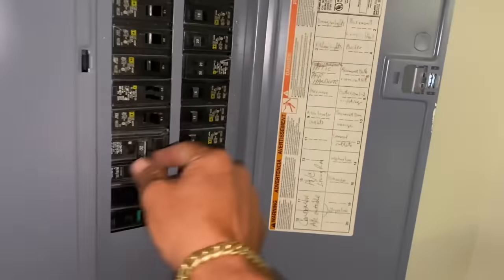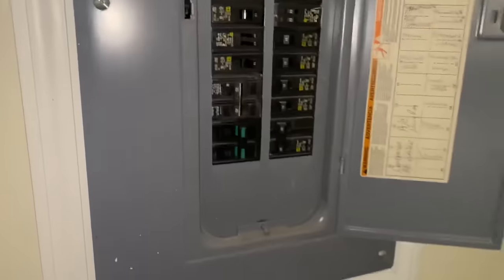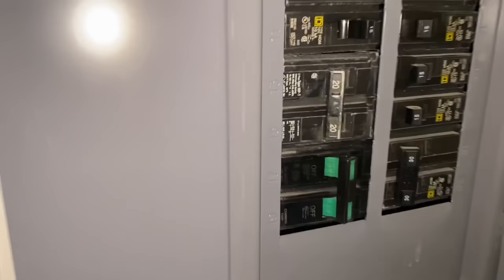We've verified no shorts to ground, so plug that back in and I'm going to check out the circuit breaker. The homeowner came to the door and startled me. I take a peek at the panel — breaker 20 is tripped. That's the AC living room. They also have a 50-amp that's tripped, for a wall unit I don't think they use anymore. We reset it — there we have it, that sounds good, she's on.